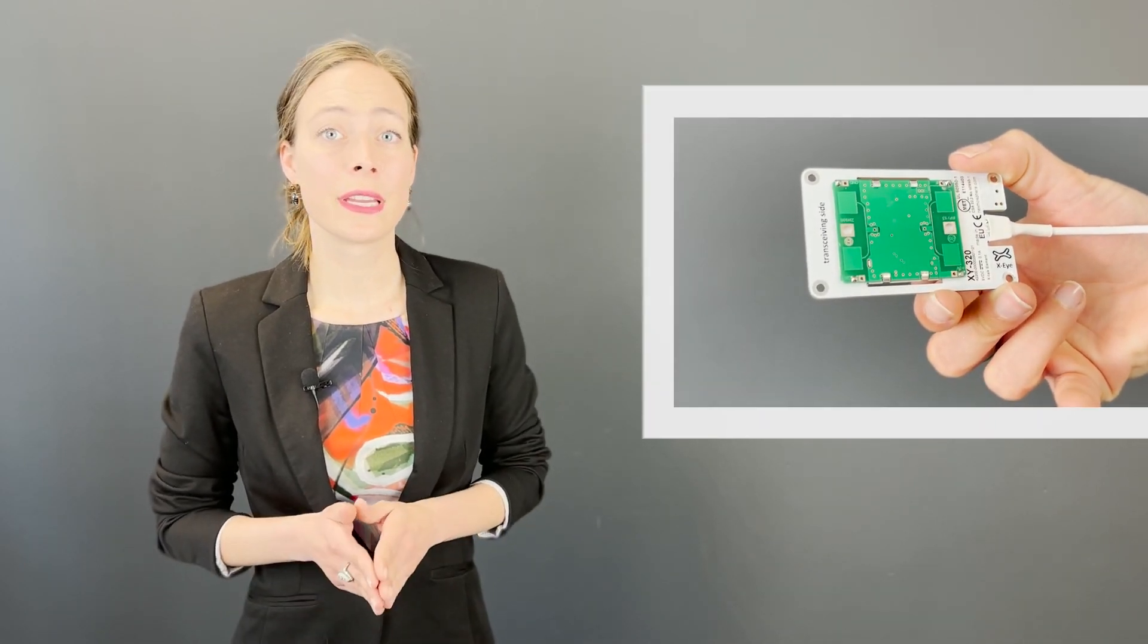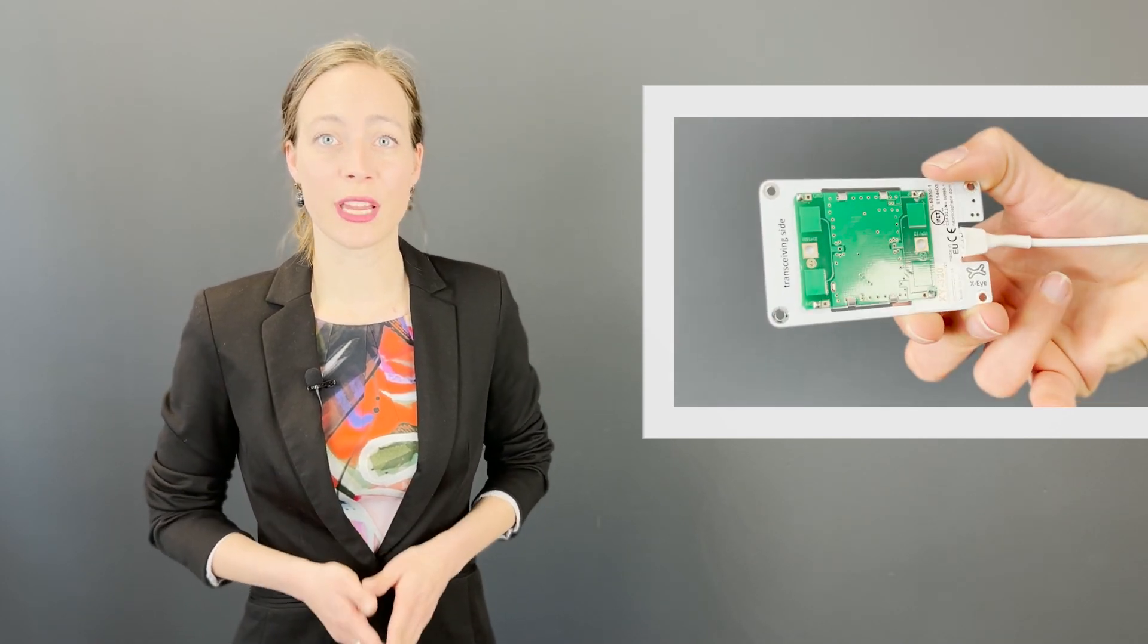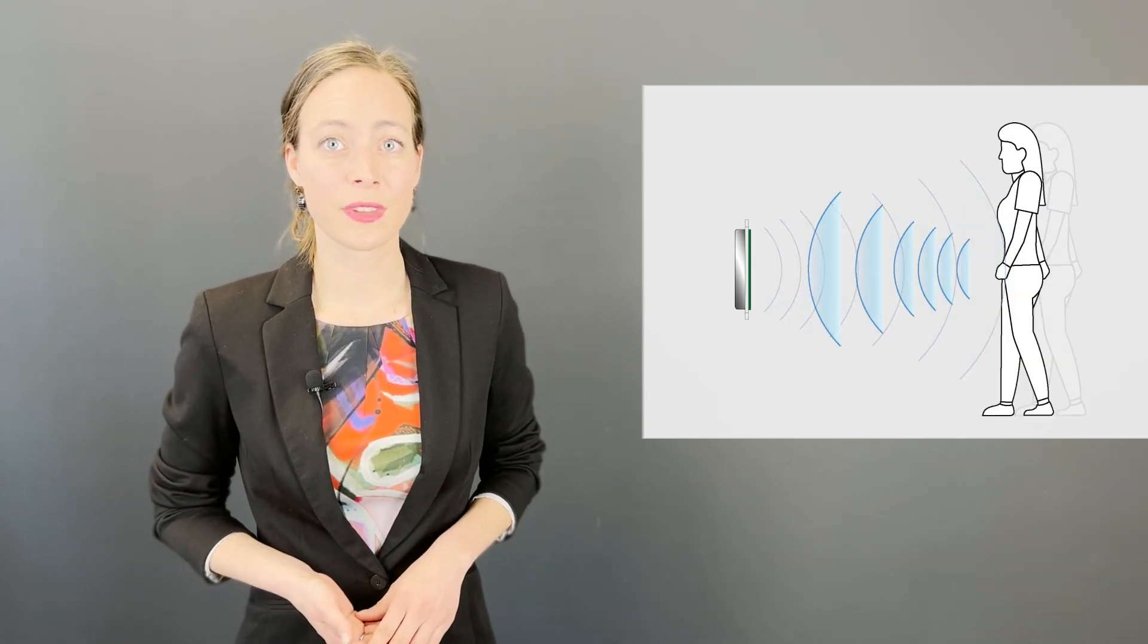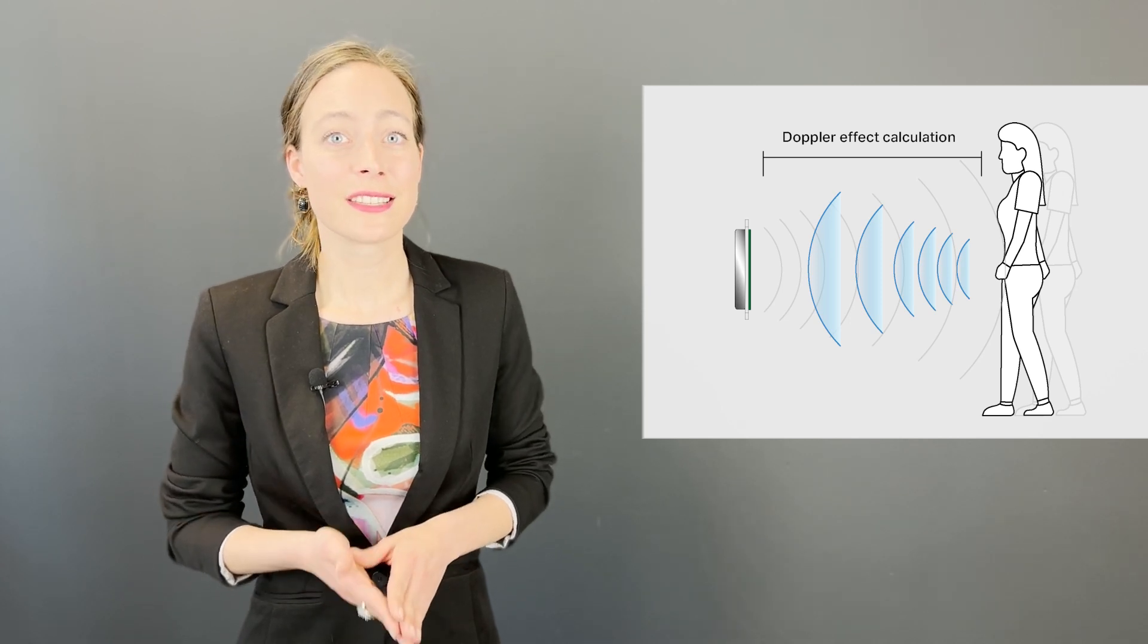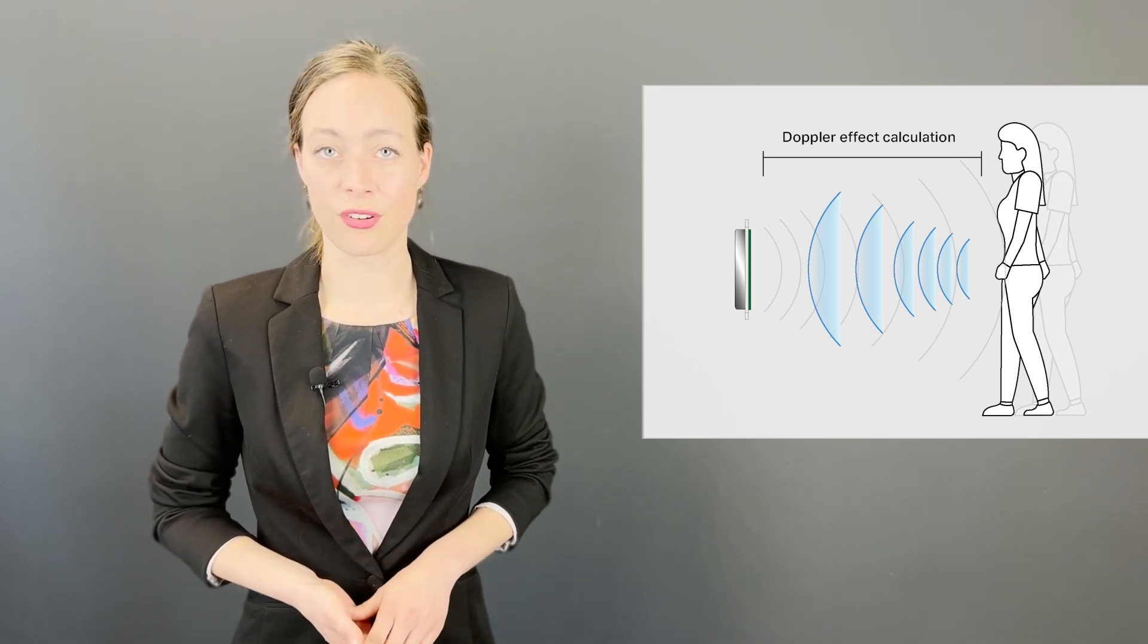The XY320 motion sensor is a rectangular sensor that can be connected to any of our experience controllers using its X-Talk cable. The sensor sends out microwaves that are reflected by people and objects. By making a Doppler calculation on the reflected microwaves, the sensor knows when people are moving within its detection area.